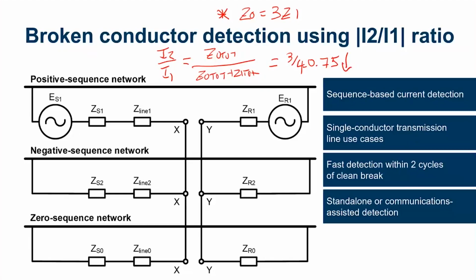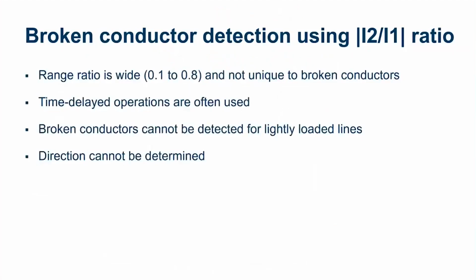As your zero sequence sources change, it makes it more difficult to detect these broken conductors using I2 over I1. Some other issues: we've got a wide range of I2 over I1, from 0.1 to 0.8, and this is not unique to broken conductors. If you've got either an in-zone or out-of-zone fault, you can also see an I2 over I1 ratio similar to this. It really becomes an issue if you've got an out-of-zone fault and you see an I2 to I1 ratio within this range. You do not want to trip, assuming you have a broken conductor or a down conductor, based off of this. To mitigate that, we use a time delay. We time delay our I2 to I1 operation, which extends the time that we have an actual broken conductor.